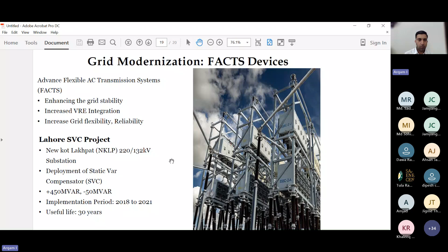reactive component of the electrical power. So we have one substation in the Lahore region, a 220/132 kV substation, where a static var compensator has been deployed, and its size is 50 MVAR, so it can supply 50 MVAR of reactive power instantly with a dynamic control system coupled with it, and it can absorb, in terms of all voltages, 450 MVAR to maintain voltage stability in the network.